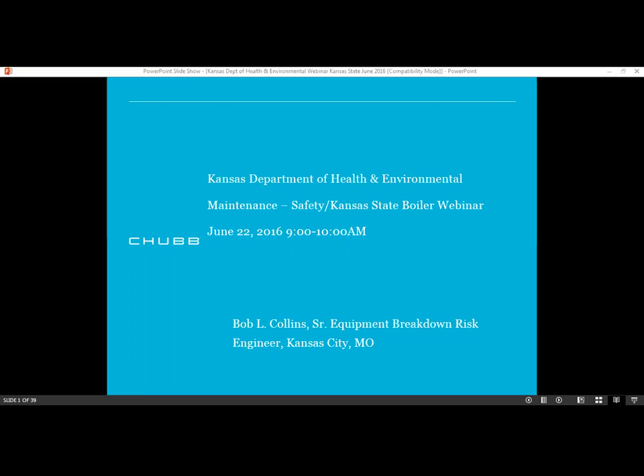And we do the internal inspections and the external inspections to check all the safety devices, very similar to what Keith had mentioned earlier. But we also take a look at other areas, more encompassing of the entire operation, whether it be a manufacturer, a municipal utility, a power plant, any kind of operation. We look at the entire equipment: the boilers, the electrical, refrigeration, air conditioning, things of that nature.